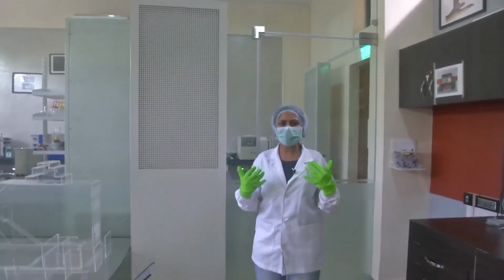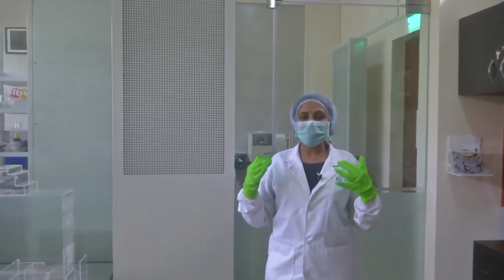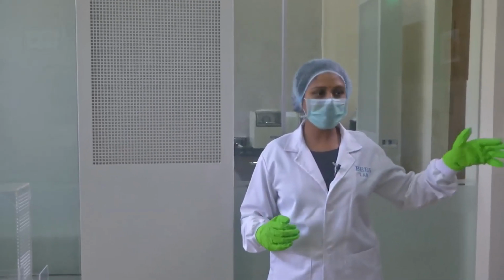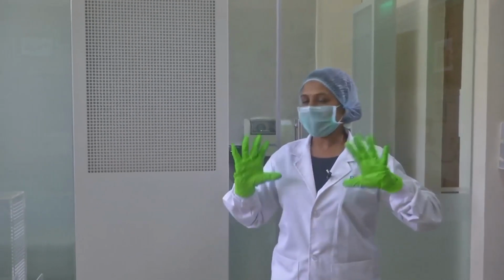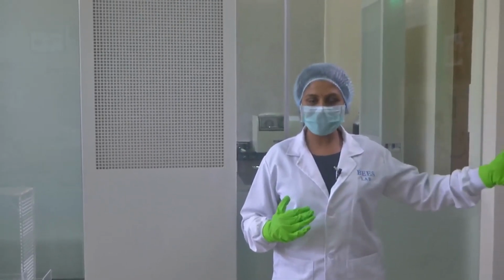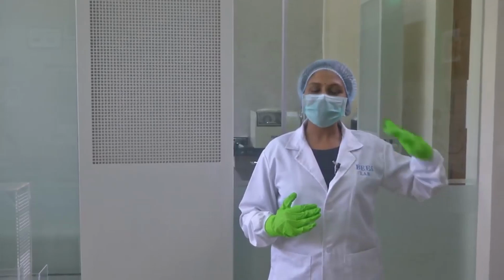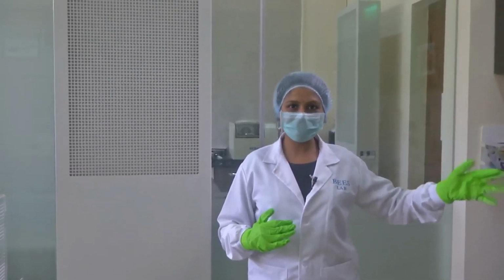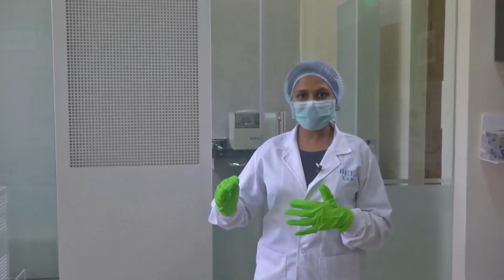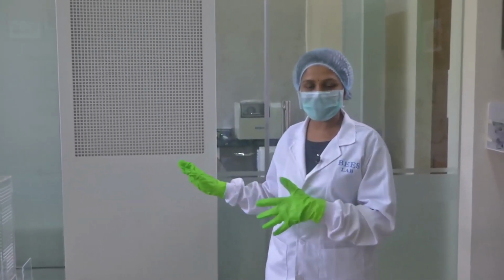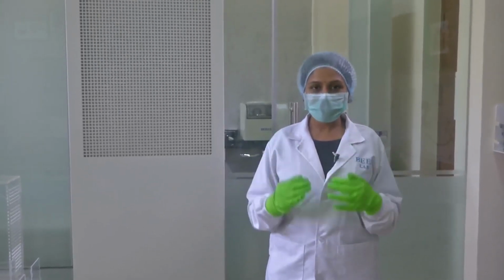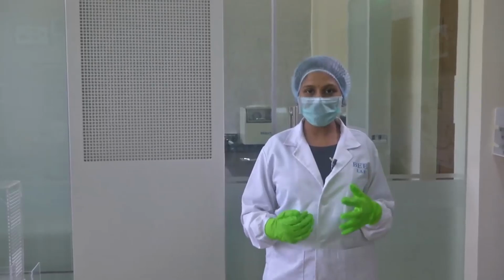So, why do you need to have an environment which has slightly higher pressure compared to the atmospheric or the outside environment? This entire room is slightly at a higher pressure compared to the outside. Just when you go beyond the door, the pressure outside is completely different, it is lower compared to the pressure here. So, we maintain this pressure using these HEPA filters, and the purpose of having higher pressure inside these rooms is just to avoid influx of air.